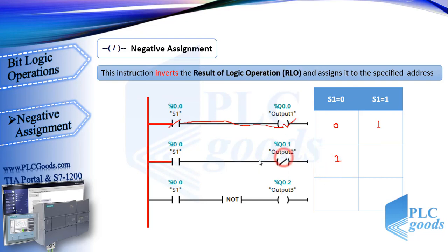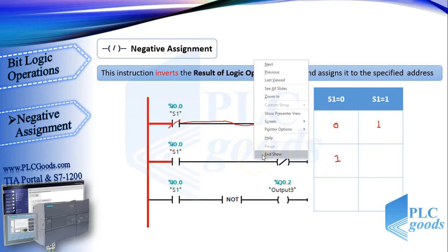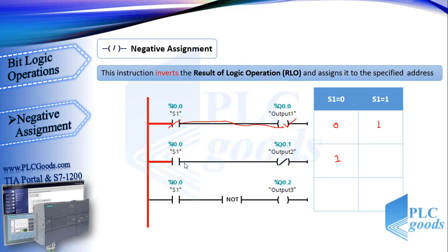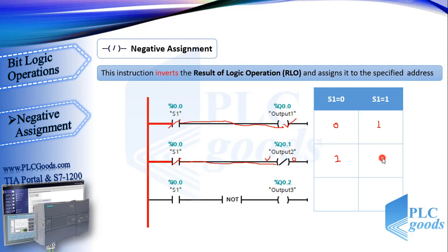Now, here we don't have virtual power, so the RLO is zero. Then negative assignment instruction inverts it to one. So this instruction makes output two be one or on. In the other state, when S1 is activated, the RLO behind negative assignment is one. So this instruction inverts it and makes output two change its state to off. As you see, there is an inverse relationship between first and second line logic.